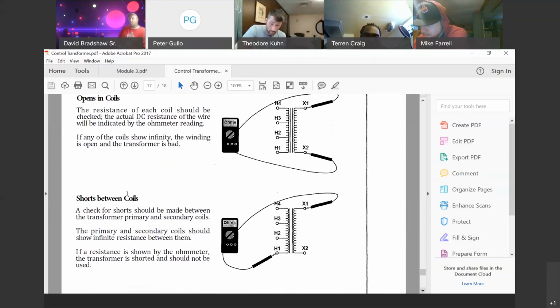A short between the coils. So if you're on the primary side, the leads don't matter, guys. If you've got black and red leads, when you're doing continuity or resistance, it doesn't matter where you have the red lead or the black lead. It doesn't matter, even with AC power. Only when you measure DC power do you want to make sure your leads are in the correct position, otherwise they'll give you the voltage but with a minus reading.